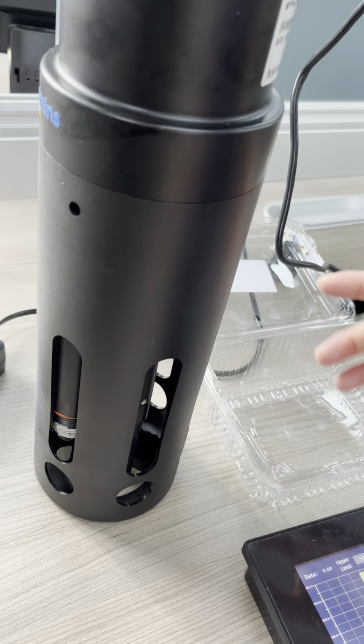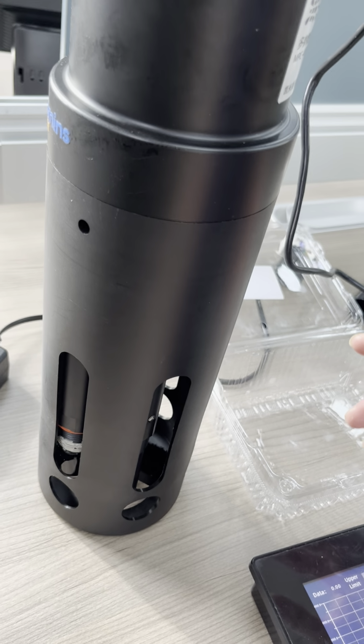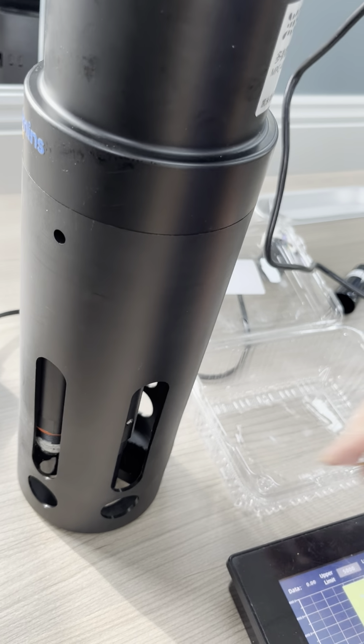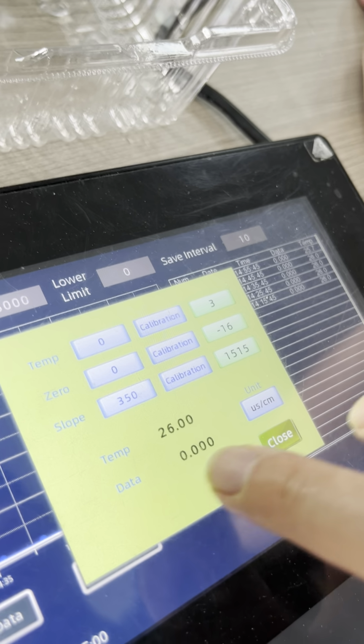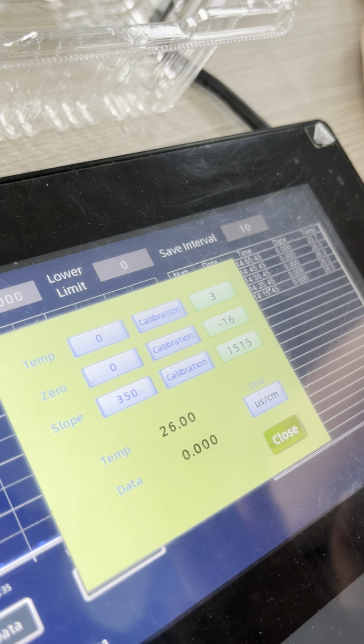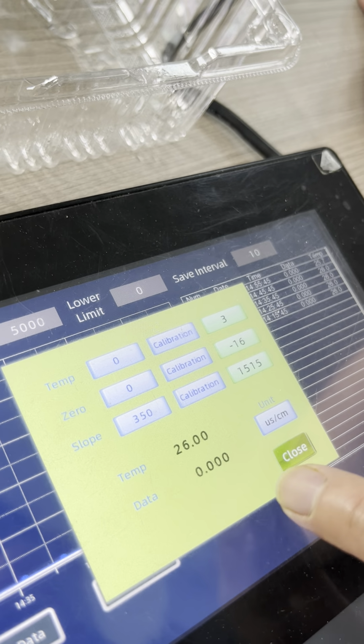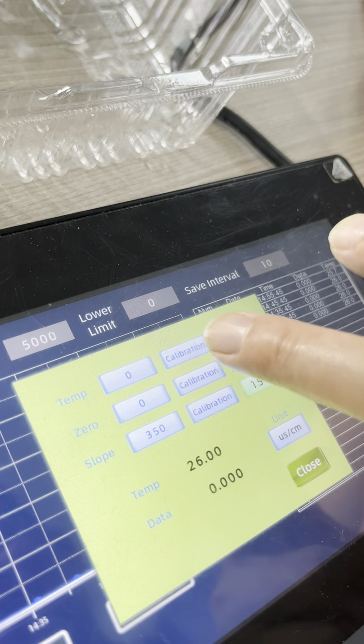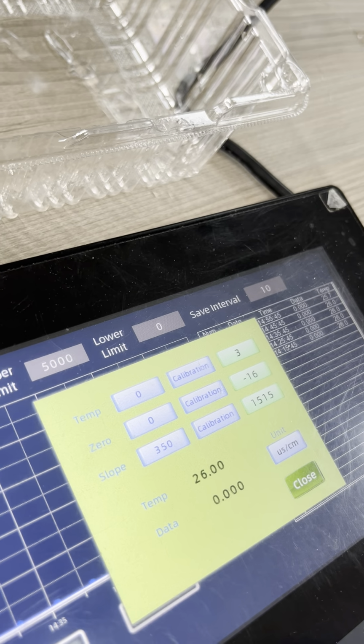There's no need to put the sensor into the standard solution. You just leave it in the air. When the data is zero, after 3 minutes, it's stable. You click calibration, the calibration is done.